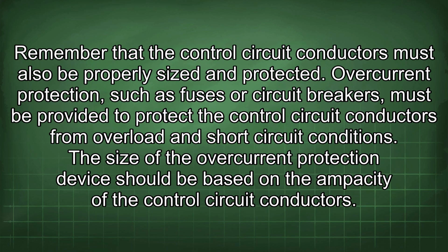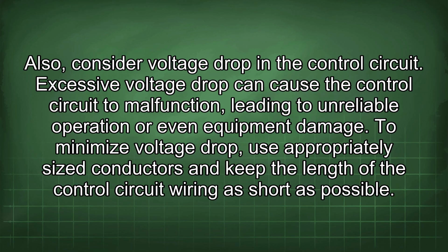Remember that the control circuit conductors must also be properly sized and protected. Overcurrent protection, such as fuses or circuit breakers, must be provided to protect the control circuit conductors from overload and short circuit conditions. The size of the overcurrent protection device should be based on the ampacity of the control circuit conductors. Also, consider voltage drop in the control circuit.